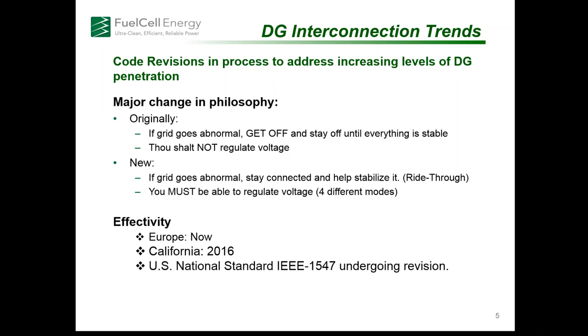But with increasing levels of DG penetration, that philosophy is changing. The new philosophy is that if the grid goes abnormal—voltage or frequency excursions—they want us to stay connected and help stabilize the grid. We call that ride-through. So instead of disconnecting and letting the utility stabilize it alone, they want our help. This is key for high levels of distributed generation penetration.